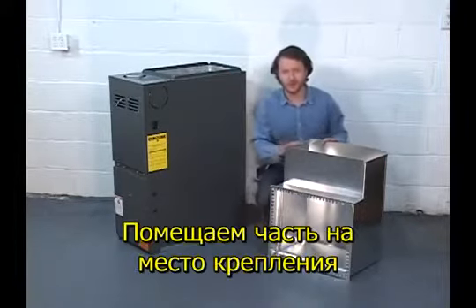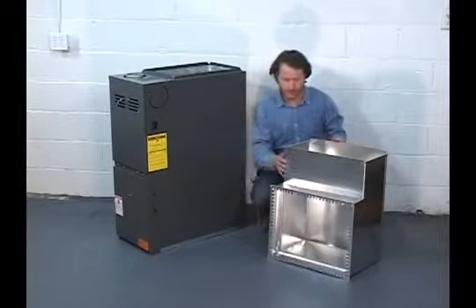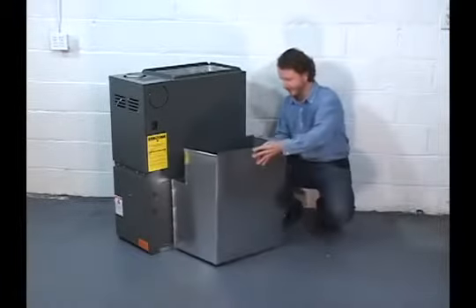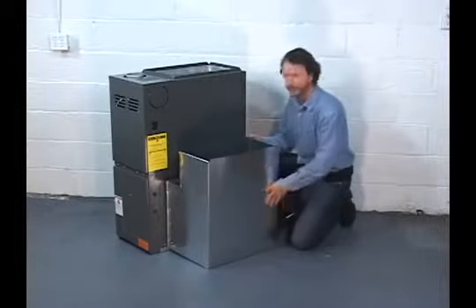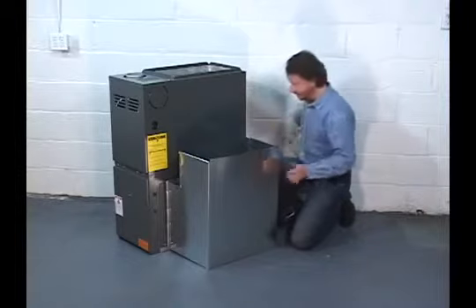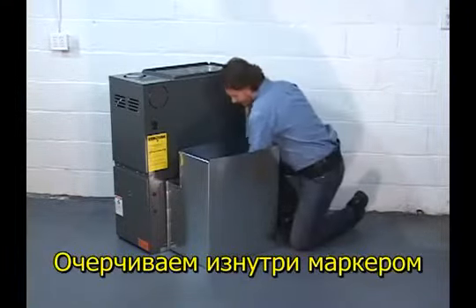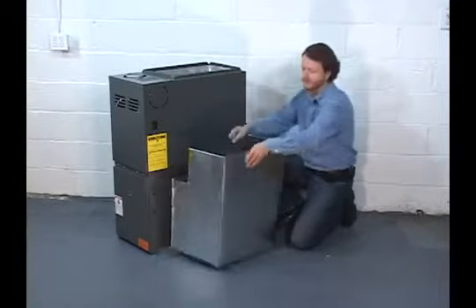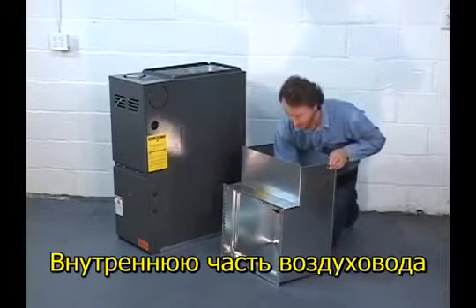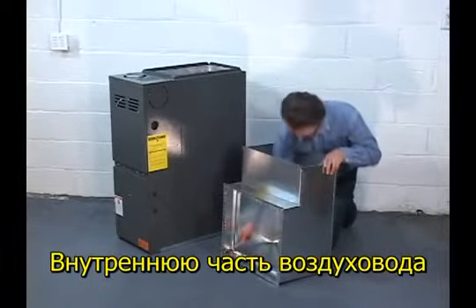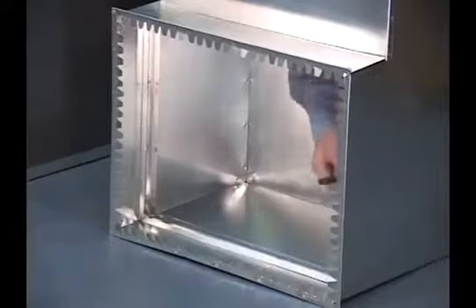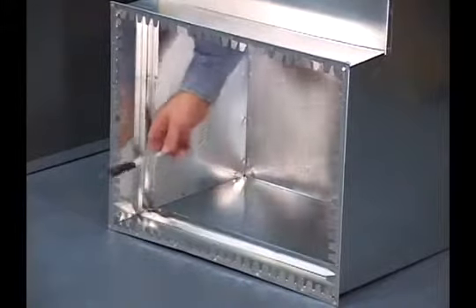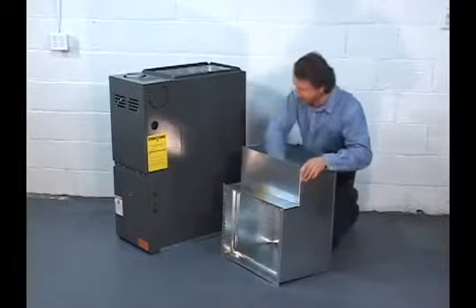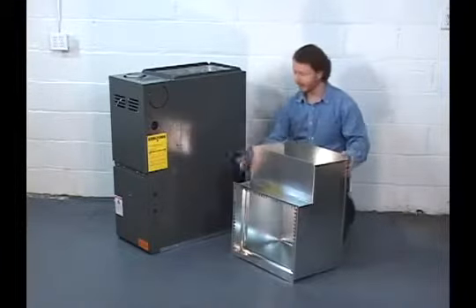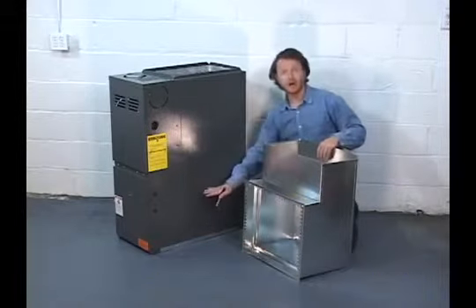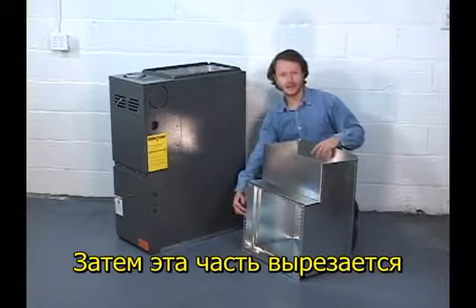Now we hook up the return air shoe or boot to the furnace. We simply put it in place on the lower left or right hand side of the furnace. Then reach inside with a marker and mark all the way around the inside rectangle onto the furnace. This shape will be marked on the lower side of the furnace, because we're going to cut a hole out the same size as the inside of the return air shoe.